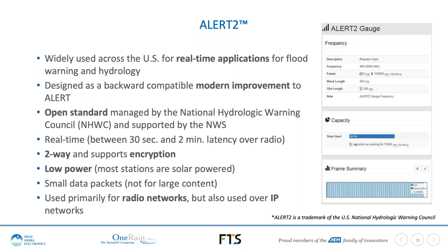Alert 2 is a two-way protocol and supports encryption for secure communications — features added to the protocol recently and now supported by vendors. It's a low-power protocol; most stations are solar powered. It transmits small data packets — not suitable for camera images, but excellent for environmental data like rain gauge and stream gauge data. While primarily used on radio networks, it is also supported over IP networks, so vendors have built interfaces to send Alert 2 content over cellular data networks.